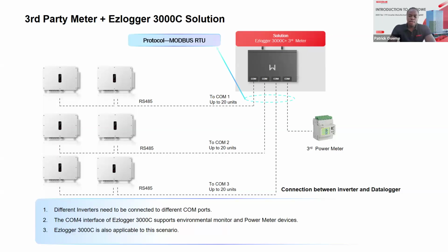And with our controller, as you can see, you can do a very large C&I. We have 3 available ports for connecting the inverters. We can do a maximum of 20 units of inverters per port. So if you do that for 3 ports, you'll have 60 inverters. Now, 60 inverters is also almost over 6 megawatts of systems installed in the C&I. And these different ports also allow you to mix the inverter types. So you can do the GT series on one, and you can do the SDT generation 3 on the other port. So you have leeway in how you can comfortably mix the inverter capacities and the inverter models, which are strictly GoodWe.